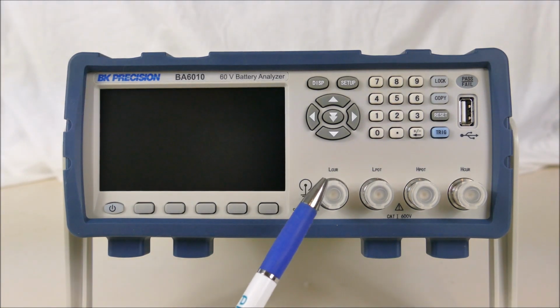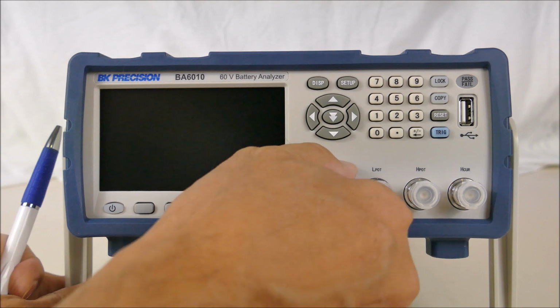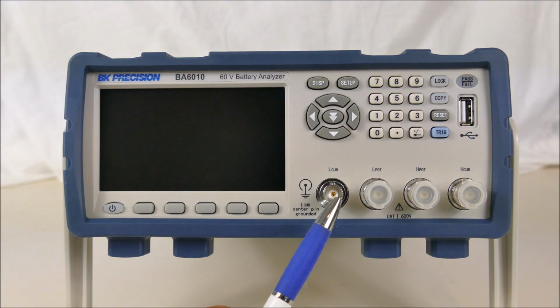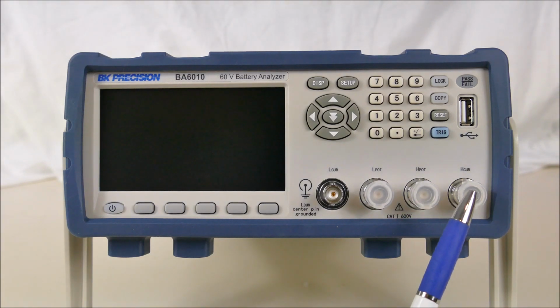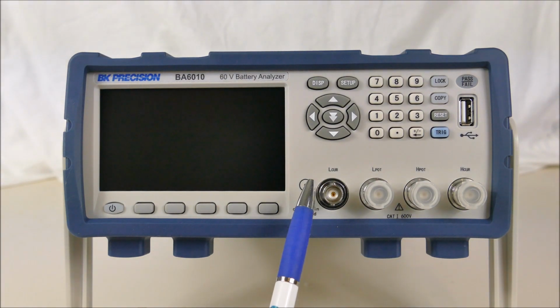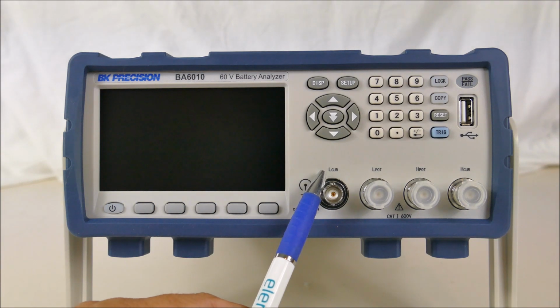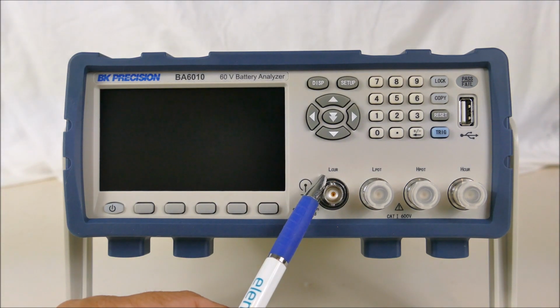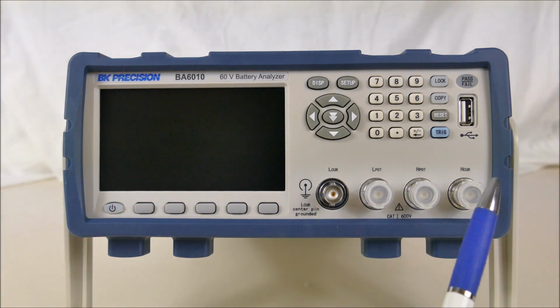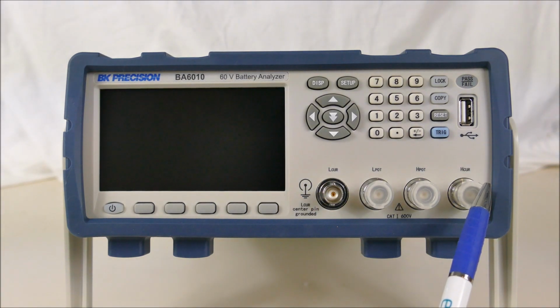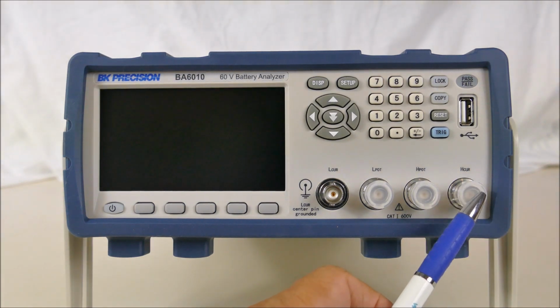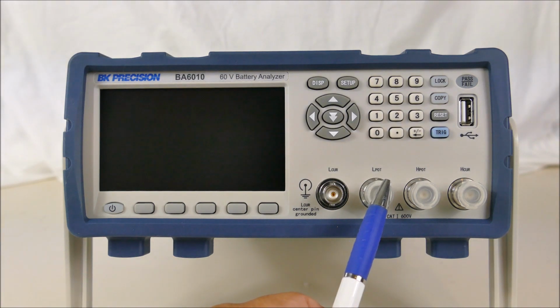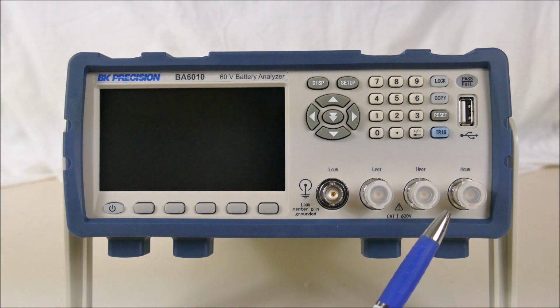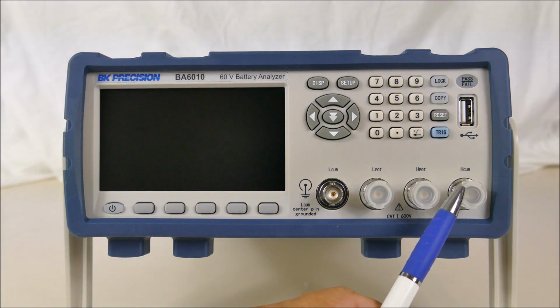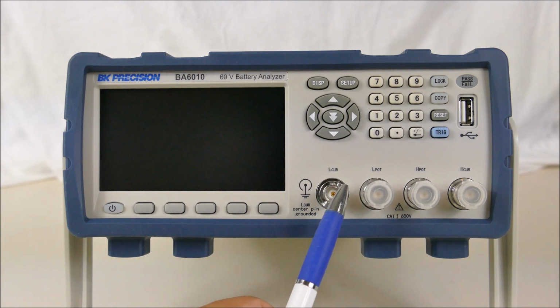And of course the connectors, we've got 4 connectors, BNC connectors, marked L-Cur, L-pot, H-pot, and H-Cur. So I assume this is a Kelvin measurement, which is a 4-wire measurement. So we've got the low terminal for the current supply, and the high terminal for the current supply. So there's a current being supplied to a load, and then the low potential and high potential terminals to measure the voltage across the load, which takes the lead resistance out of the measurement.